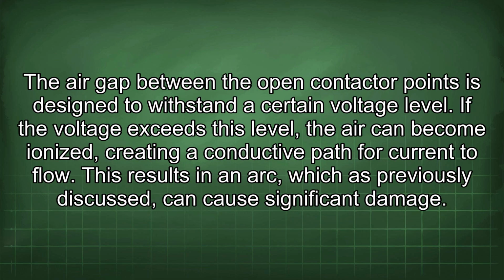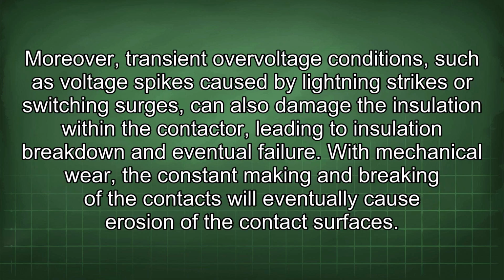The air gap between the open contactor points is designed to withstand a certain voltage level. If the voltage exceeds this level, the air can become ionized, creating a conductive path for current to flow. This results in an arc, which, as previously discussed, can cause significant damage. Moreover, transient overvoltage conditions, such as voltage spikes caused by lightning strikes or switching surges, can also damage the insulation within the contactor, leading to insulation breakdown and eventual failure.